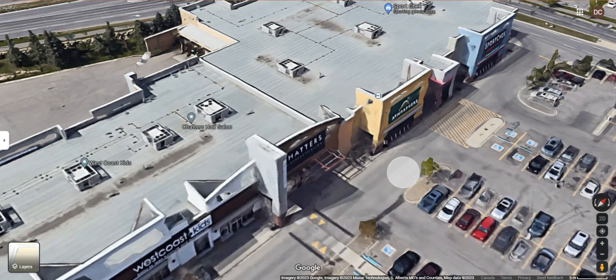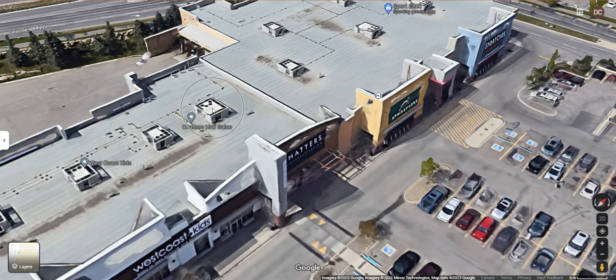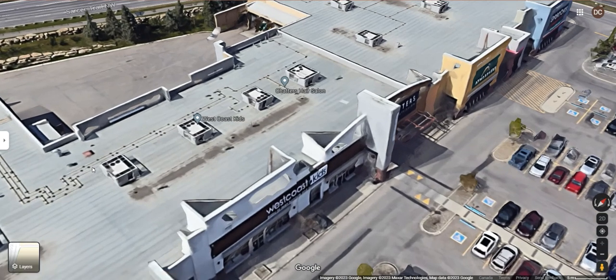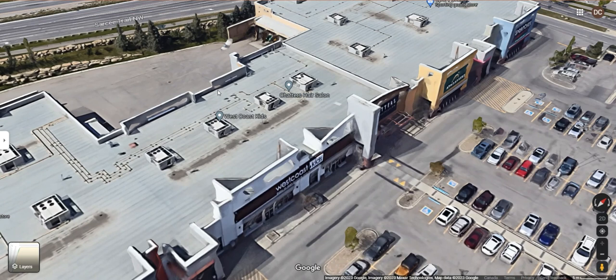Back to our retail setting — zooming in on this place, you can see there's one tenant here taking up this area, and they have this one unit distributing air to their entire space. The tenant over here took three bays, so they have three units to distribute air into their space. The reason it's designed this way is that potentially this could be four tenants with walls put in between each one, and each tenant has a rooftop unit to attach to. A bigger tenant just happens to get more units.